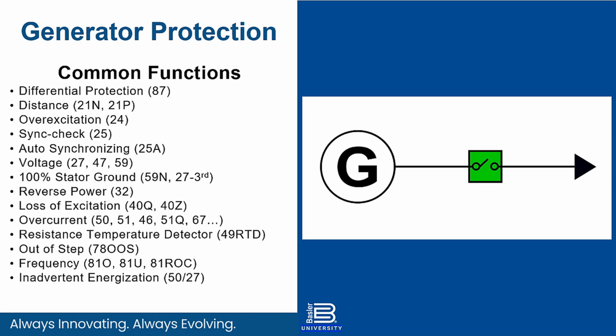And a couple of the other ones that are semi-unique to generator-based applications are out of step... what was the other one I was looking for? The 40Z or the 40Q I'd already mentioned. We can additionally do 100% stator ground by using a 59N and an undervoltage third harmonic view.